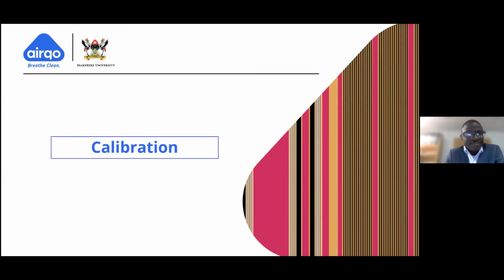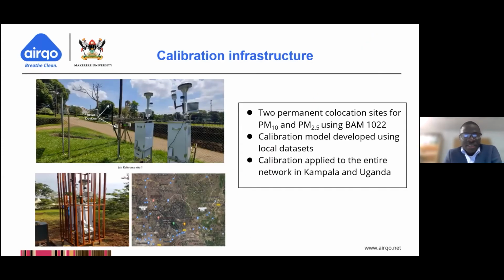Yeah, so I'm going to talk specifically about the calibration. The infrastructure setup is that you have a network of 120 devices. So, the question of will the low cost sensors eventually replace the reference monitors? Maybe at some point, but at the moment we see the two approaches working side by side, to the extent that we need the reference monitors to support the quality control of the low cost sensors. And in our case, we're using two reference monitors to set up a permanent co-location infrastructure where we develop a calibration model and then apply it to the network in Kampala and Uganda. The two reference monitors, a BAM 1020 and 1022, for PM10 and PM2.5, support the calibration of the rest of the network.